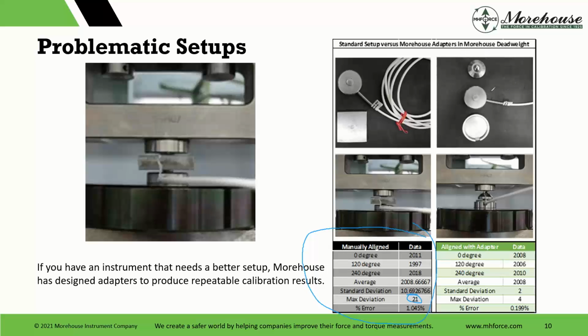When we use these adapters, and these adapters happen to be ones that we designed and made, if you get me on a tangent, I'm going to say, hey, load cell manufacturers, and we're included in this group, are a bunch of idiots sometimes because no one standardized anything, right? This load cell here should be pretty simple. Any 5,000-pound button load cell, why didn't they make the same button, the same base? No, every manufacturer made it different. So we have a lot of adapters for a lot of different load cells, which is costly. And somebody complained to me in one of my training classes, why are your adapters so much? Because we're not in the business of making 500 of these adapters. Typically a lab might have a need for one, and we might get an order for one every 2 months.